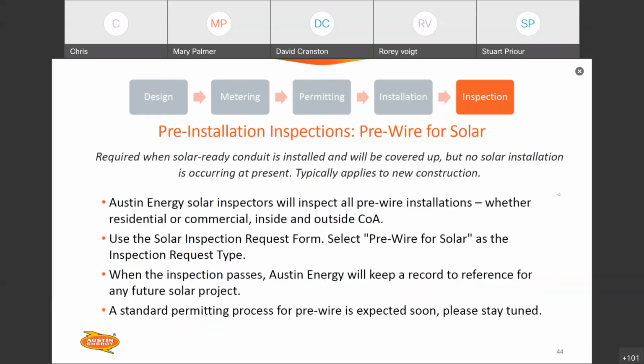Pre-wire for solar is another type of pre-installation inspection. Unlike the other types of inspections, with pre-wire you're just putting in solar-ready conduit for a future solar installation, when there's no current solar installation happening right now. Mostly this is new construction. A lot of these new construction homes want to be solar ready, so if you are the contractor putting in that conduit, which is usually empty conduit, please call for a pre-wire inspection with us so we can check that conduit and make sure it's all good to go before it gets covered up and before that new construction project gets full approval from the city.